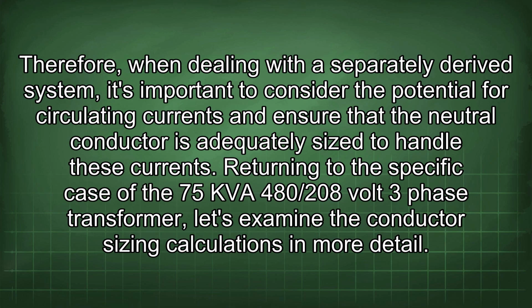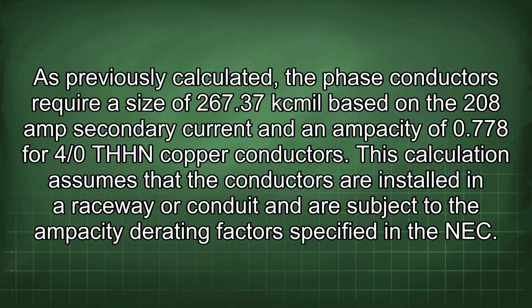Returning to the specific case of the 75 kVA 480/208 volt three-phase transformer, let's examine the conductor sizing calculations in more detail. As previously calculated, the phase conductors require a size of 267.37 kcmil based on the 208 amp secondary current and an ampacity of 0.778 for 4/0 THHN copper conductors. This calculation assumes that the conductors are installed in a raceway or conduit and are subject to the ampacity derating factors specified in the NEC.